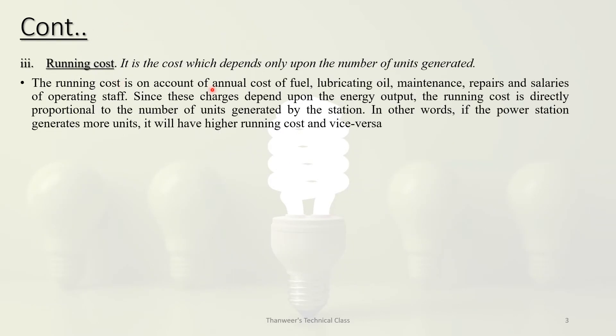Running cost is the cost which depends only upon the number of units generated. It is on account of annual cost of fuel, lubricating oil, maintenance, repair, and salaries of operating staff. Since these charges depend upon energy output, the running cost is directly proportional to the number of units generated. If the power station generates more units, it will have a higher running cost, and vice versa.